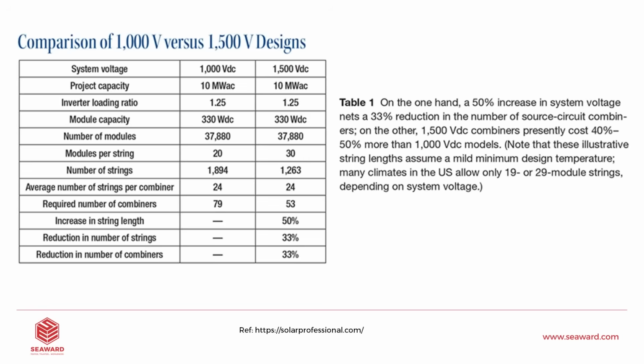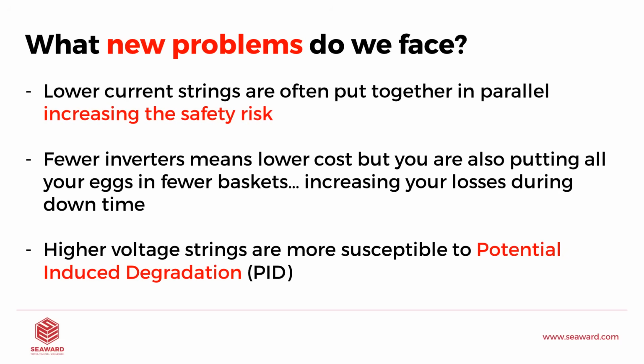However, when we look at it holistically, the average number of strings per combiner stays the same at 24, but the number of strings overall is really reduced, and the number of modules per string is increased. So overall, this really brings our cost down quite significantly with regard to balance of systems and with regard to labor. So this is all well and good. We're going to save a lot more money. We can become independent from government subsidy and tax credits because we're offering a very stable return on investment to our client without the need for any kind of governmental assistance.